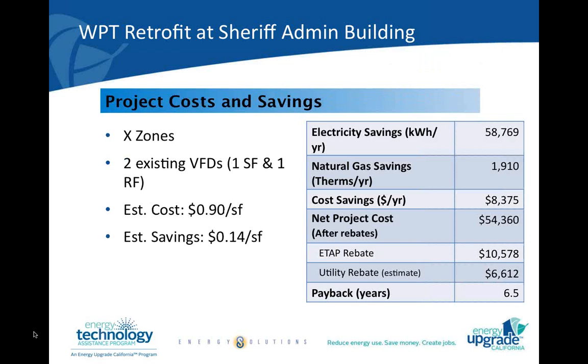Next slide, please. So this project had X zones. That was really 100 zones. We have 2 existing VFDs. Estimated cost for this project is 90 cents a square foot, and estimated savings about 14 cents a square foot. Energy savings about 59,000 kilowatt hours, with gas at about 2,000 therms per year. Cost savings at $8,400, which translates to about 5% of the energy associated with that facility, and that's including the central plant energy that we get next door. The payback is about 6.5 years.